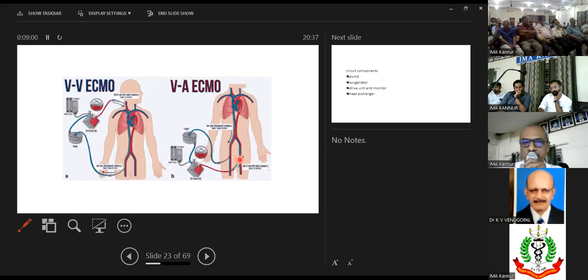So basically, these are the two types of extracorporeal life support. Everything which comes is some modification of one of these two. You have many minor differences, but those are all patient to patient dependent. Now, when you're thinking of starting a patient on ECMO, you need several components: the pump, the oxygenator, the drive unit and the monitor for the pump, and a heat exchanger. Now, each of these is a separate component, but they all need to work together as a system to ensure that you get a good outcome.